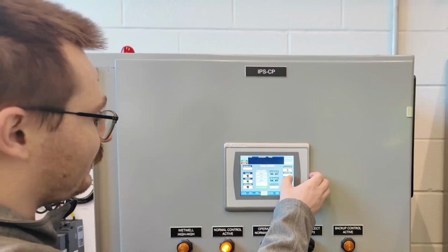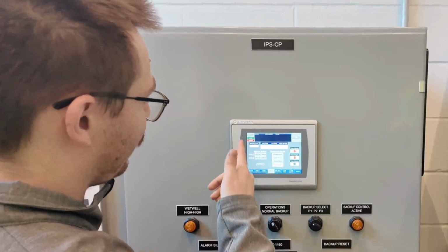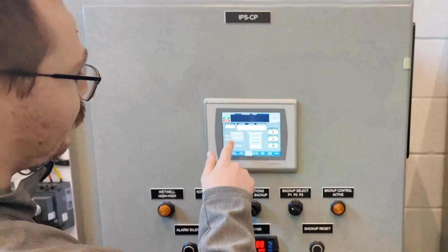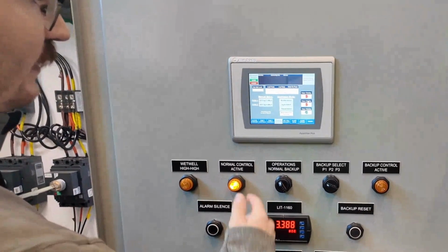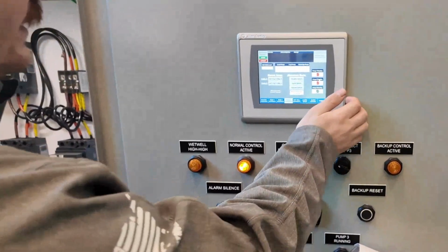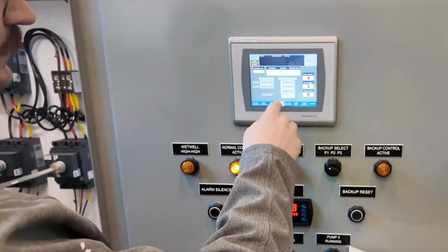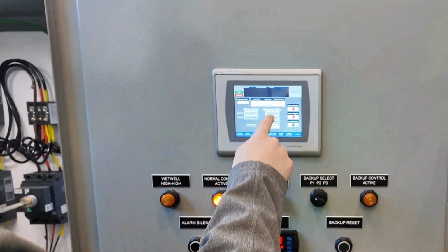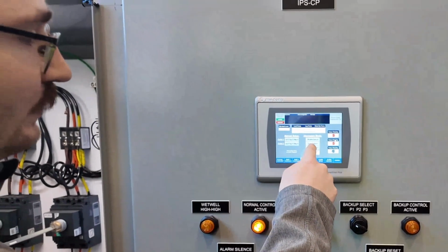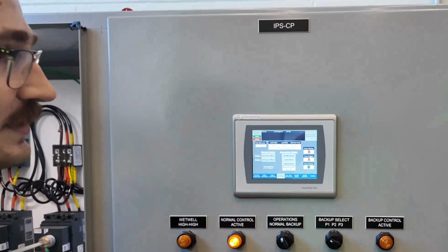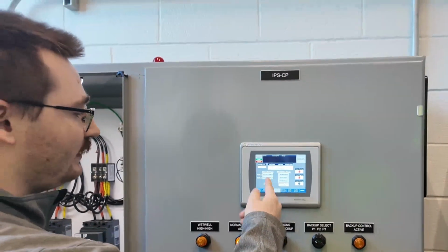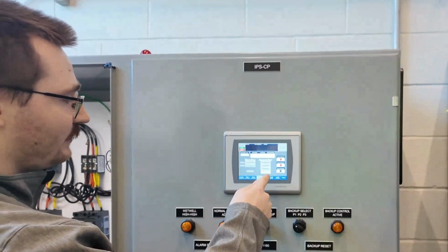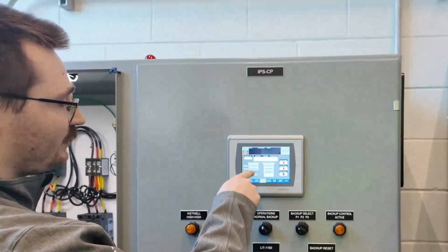We have additional screens for alternation select. The operator, if you're not logged in, you won't be able to change between manual set points and alternation mode. So you have to log in to be able to select that. So in alternation mode, you have the options to disable it, use a cycle based, which is going to automatically, each time a pump runs, the next pump's going to run the next time, or you can manually select it. So right now it's in auto, so if I go to manual, then you can choose this.